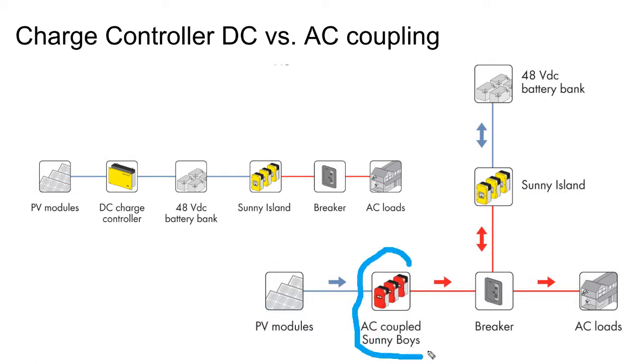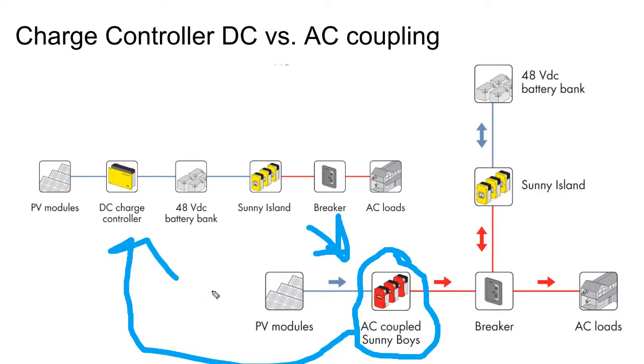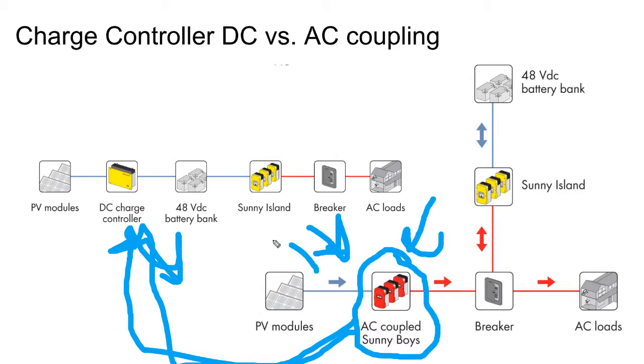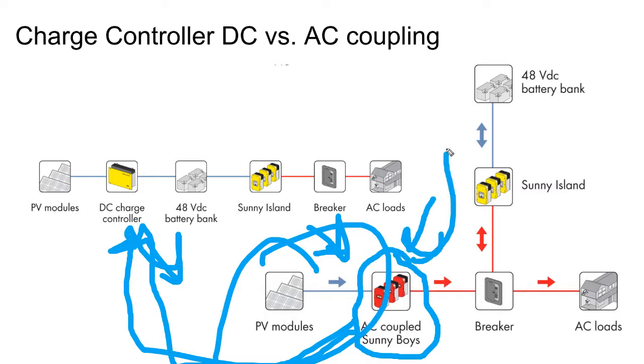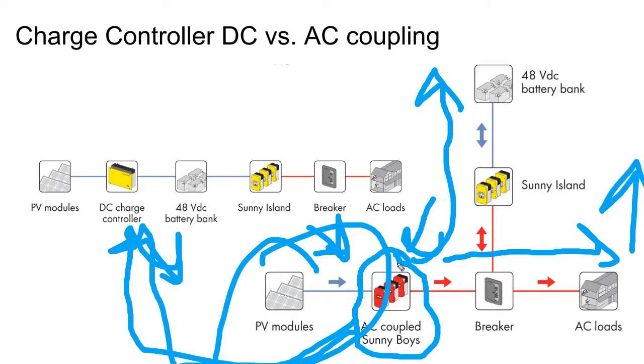But in reality, we have had so much research and development and economies of scale go into these batteryless inverters that they're about the same price as the charge controllers, and about the same efficiency. And then most of the power from your grid-tied solar array is not going to go into your battery bank, but instead is either going to go into your load or the grid itself. And so it doesn't really matter if you do DC or AC when you're grid-tied.